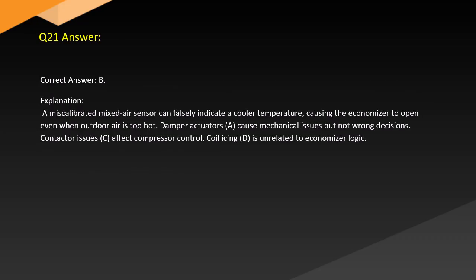Answer. Correct answer: B. Explanation. A miscalibrated mixed air sensor can falsely indicate a cooler temperature, causing the economizer to open even when outdoor air is too hot. Damper actuators A cause mechanical issues but not wrong decisions. Contactor issues C affect compressor control. Coil icing D is unrelated to economizer logic.